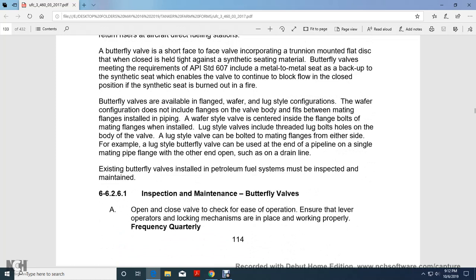A butterfly valve with a short face incorporates a trunnion-mounted flat disc held tight with synthetic seating material. Butterfly valves that meet the requirements of API Standard 607 include a metal-to-metal seat as a backup to the synthetic seat, enabling the valve to continue to prevent backflow in the closed position if the synthetic seat is burned out in a fire. Butterfly valves are available in flange, wafer, and lug type configurations. The wafer configuration is designed with the valve body fitting between the mating flanges and installed in the piping, with the wafer style centered inside the flange bolts of the mating flanges when installed.